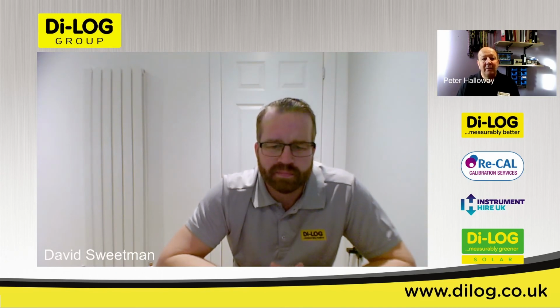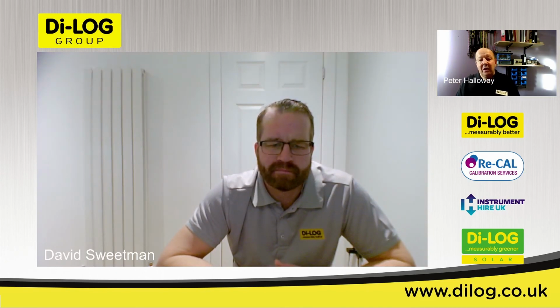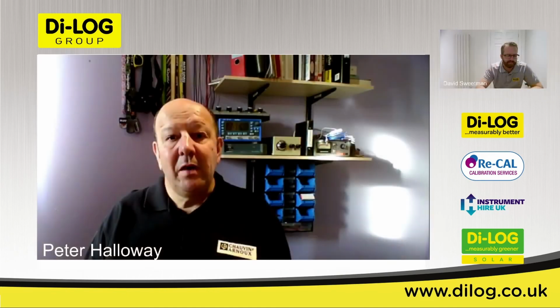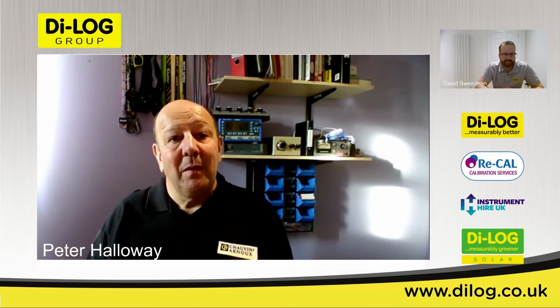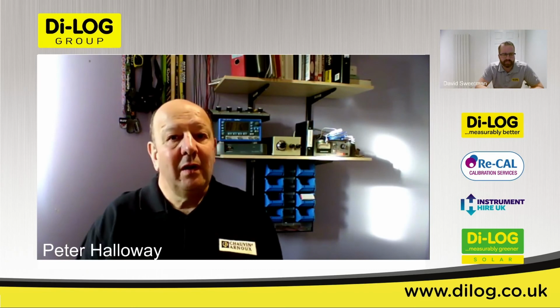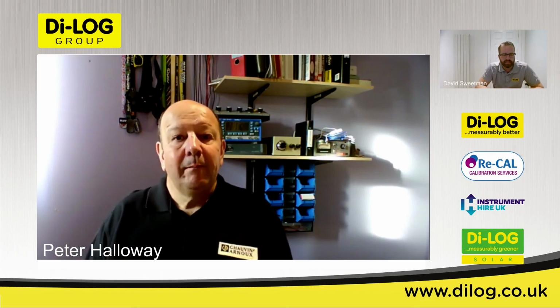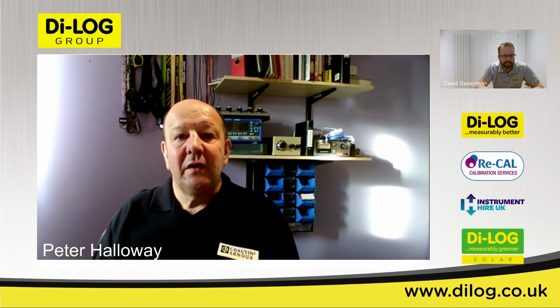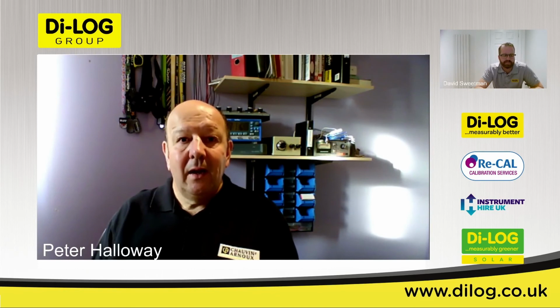Yeah, absolutely, Dave. Interesting enough, LEDs typically are a capacitive load, so they help in that respect — they might not give you a power factor issue. They're more likely to be causing harmonics, and LED lighting typically causes third harmonic issues. So it's just something to bear in mind.